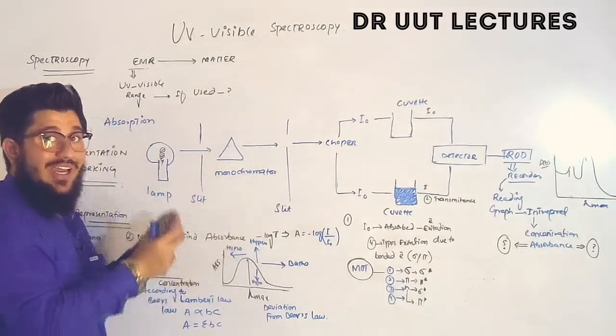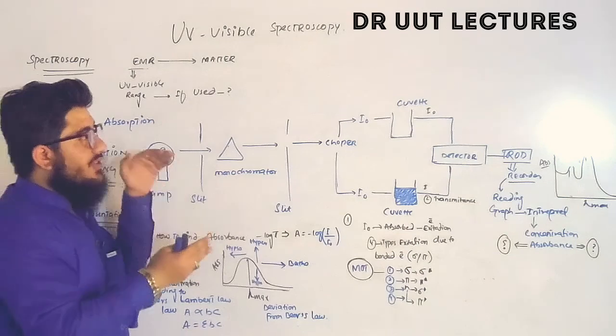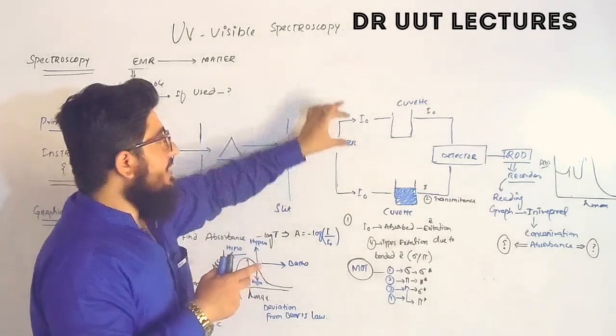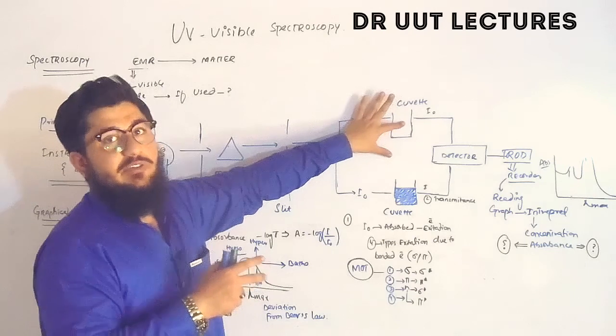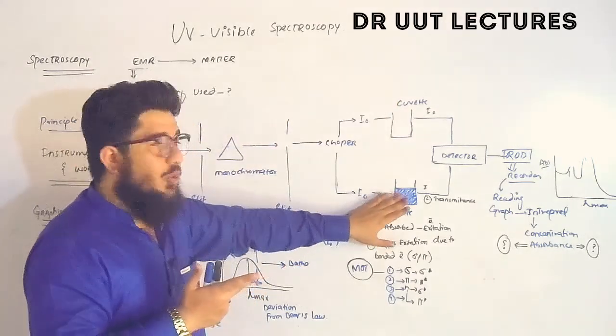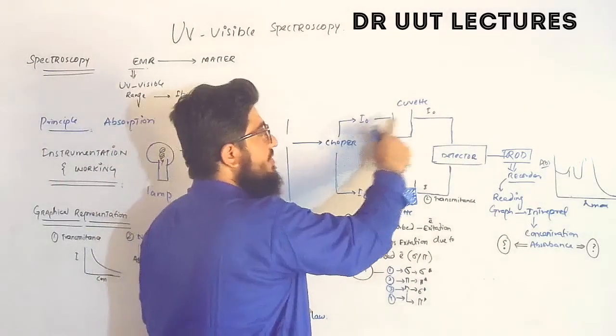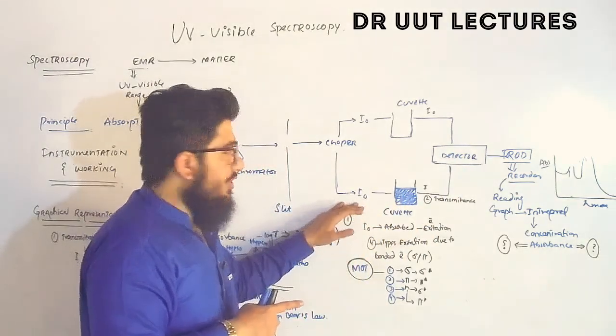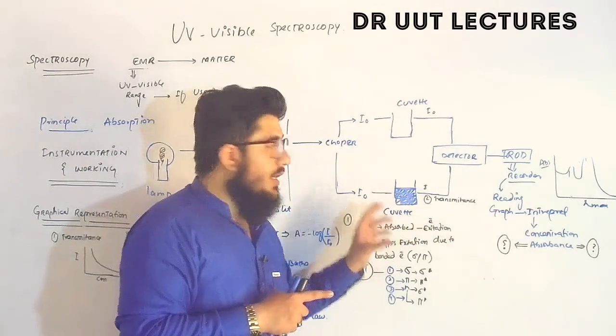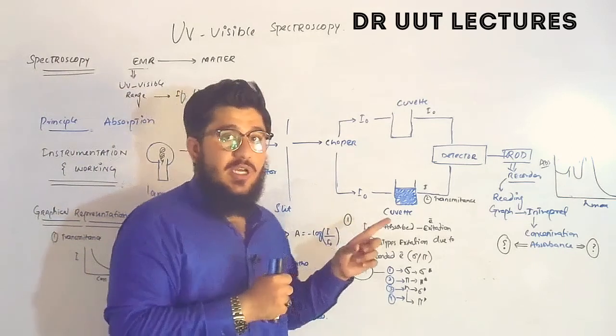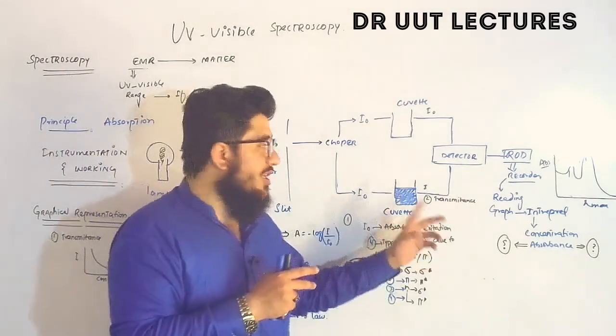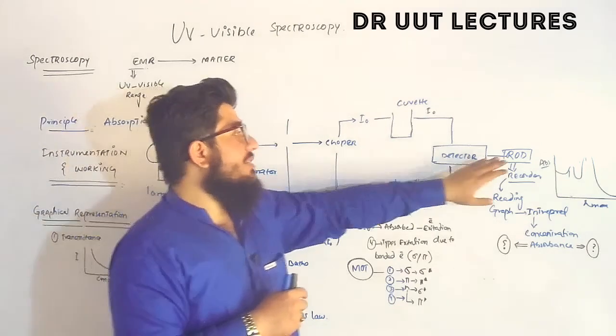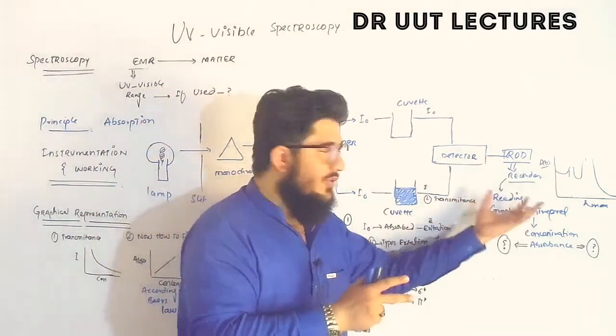Slit two further adjusts the radiation, then it is targeted toward the chopper. The chopper splits the radiation into two beams. One beam passes through a cuvette containing only buffer solution, and the other passes through a cuvette containing the sample. The radiation through the buffer cuvette is unchanged and directed to the detector. The sample absorbs some radiation, and the remaining transmitted radiation is also forwarded to the detector.